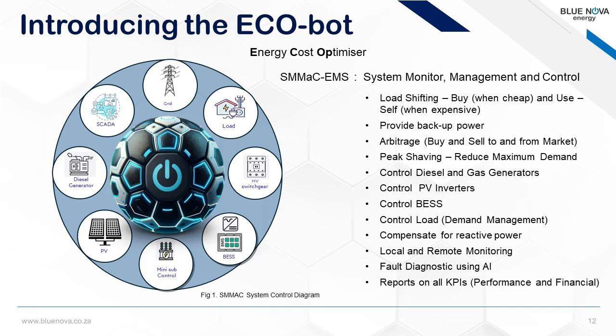Peak shaving to reduce maximum demand is a function that is essential. Controlling the diesel and gas generators, essential. Controlling the PV inverters, and controlling the battery energy storage system, all functions of the SMMaC. And then, very important, when such an EcoBot system or a battery energy storage system is sized that it cannot handle the complete load, one would then have to optimize the size of the load through means of load control, essentially disconnecting some of the critical or non-critical loads during periods when the system has to run independently from the grid. And of course, compensating for reactive power, which reduces your maximum demand and also leads to savings.